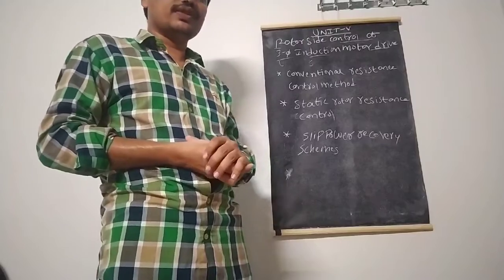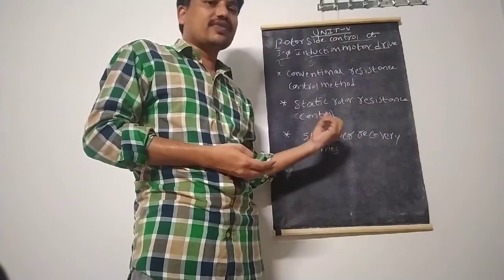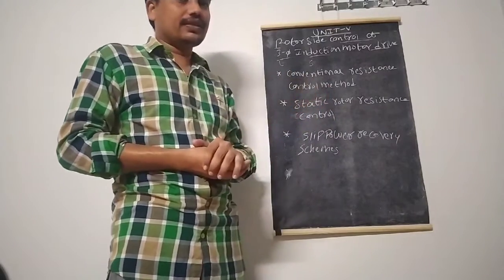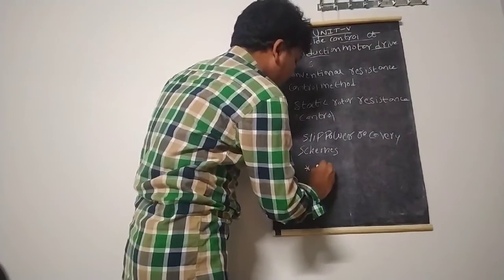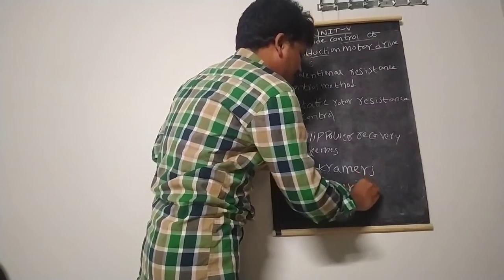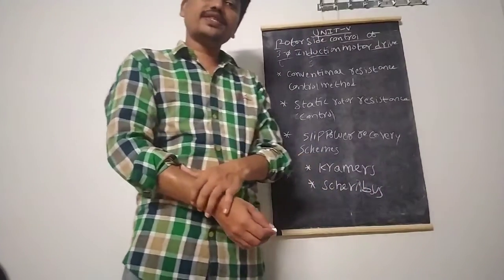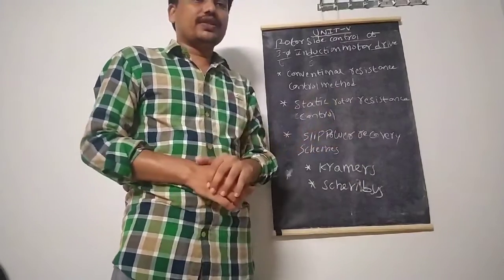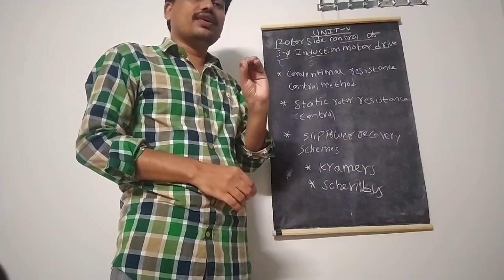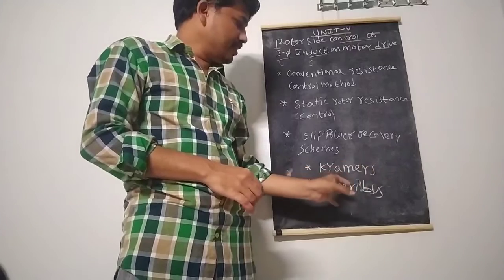The third method is the slip power recovery scheme, which controls the speed of the motor and recovers the slip energy. There are two kinds of methods: the first is the Kramer drive system, and the second is the Scherbius drive. The Kramer drive is further subdivided into conventional and static types, and similarly the Scherbius drive has conventional and static types. However, since the conventional types are not in our syllabus, we directly go through the static methods — the static Kramer drive and the static Scherbius drive.